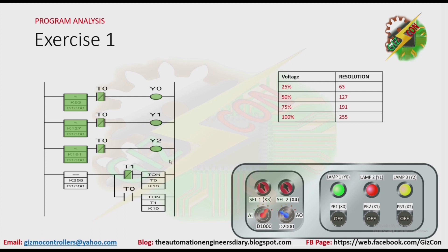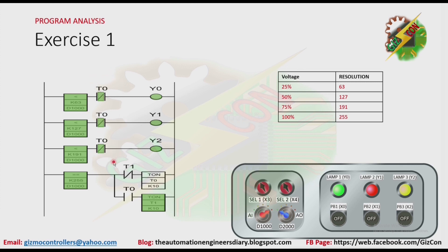As you can see here, the value of the analog signal is 100%. This condition is satisfied — that will make T0 activate after 1 second. When T0 is activated, the normally open contact of T0 will be closed, and the normally closed contact of T0 will be open, making Y0, Y1, and Y2 turn off. Because of this, T1 will be activated after 1 second. When T1 is activated, the normally closed contact of T1 will be open, making T0 turn off. Because T0 is off, the normally closed contact of T0 goes back to its initial state, and T1 will be deactivated. The cycle will just repeat.